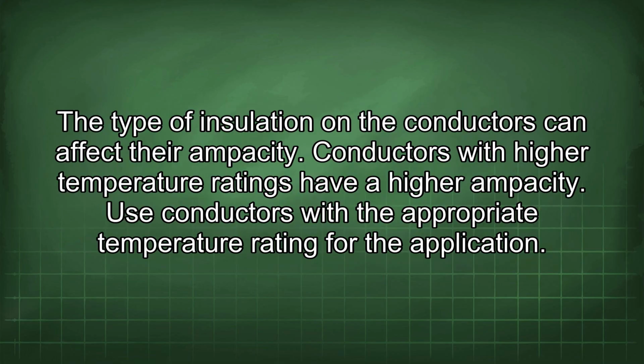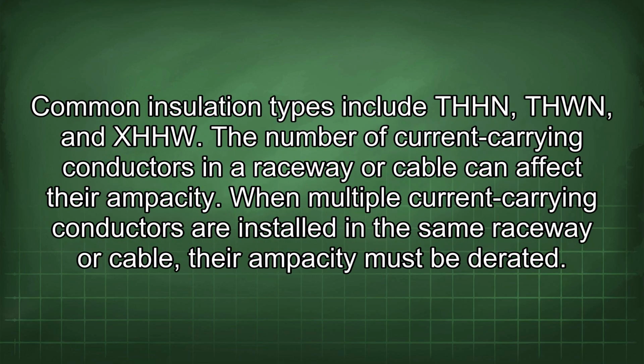The type of insulation on the conductors can affect their ampacity. Conductors with higher temperature ratings have a higher ampacity. Use conductors with the appropriate temperature rating for the application. Common insulation types include THHN, THWN, and XHHW.